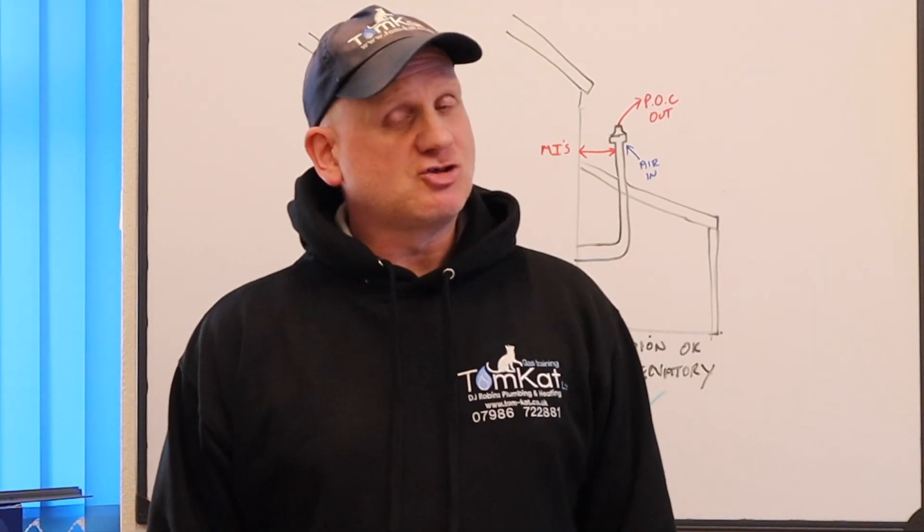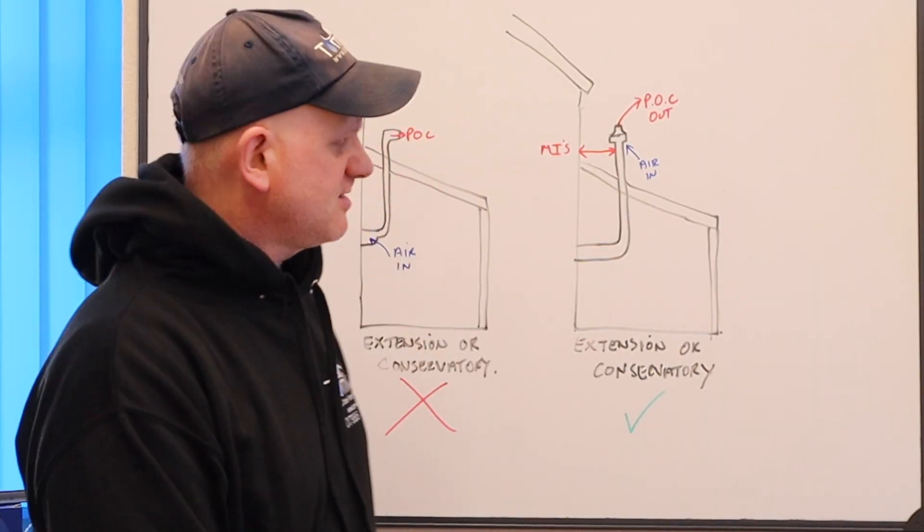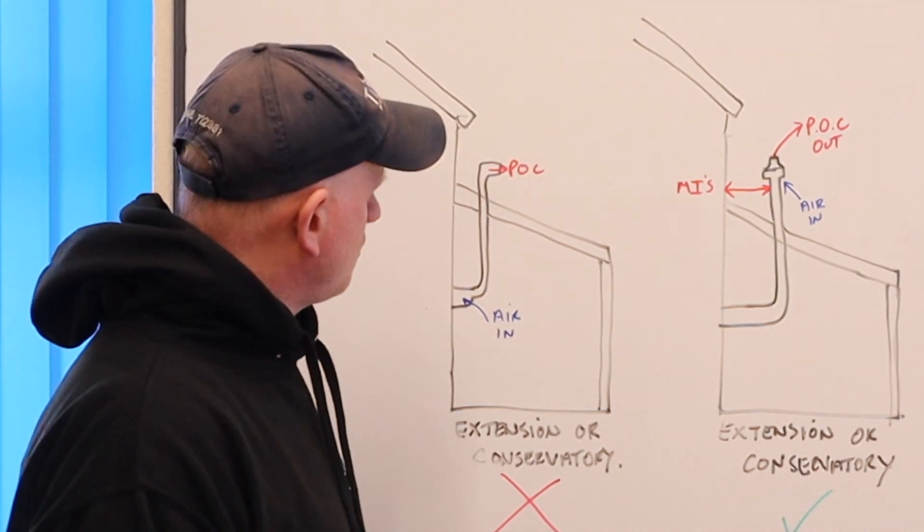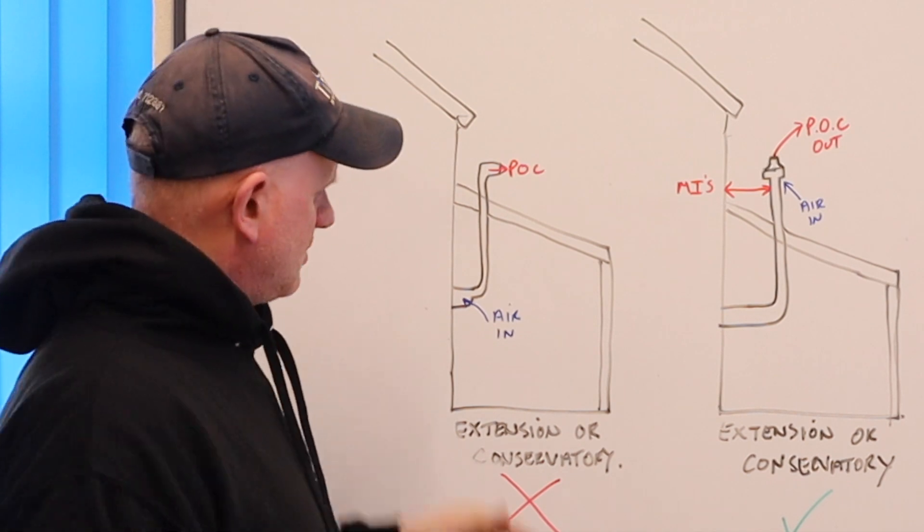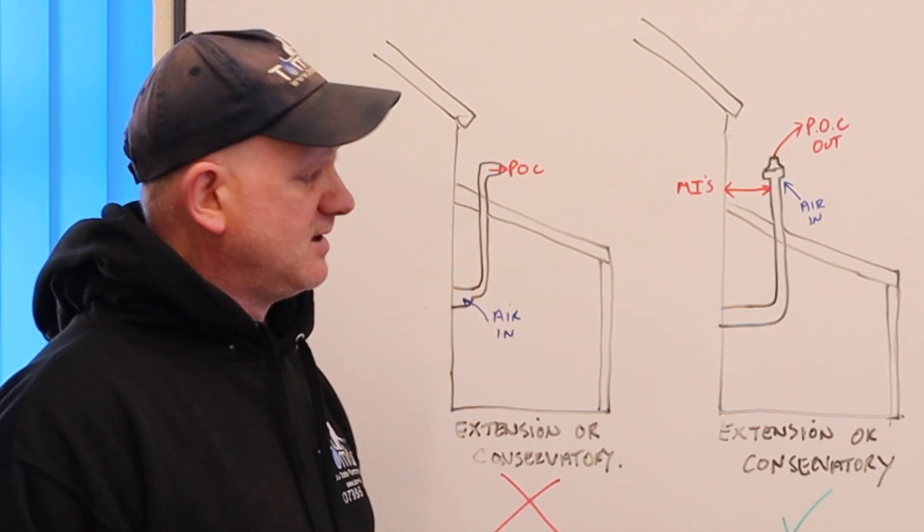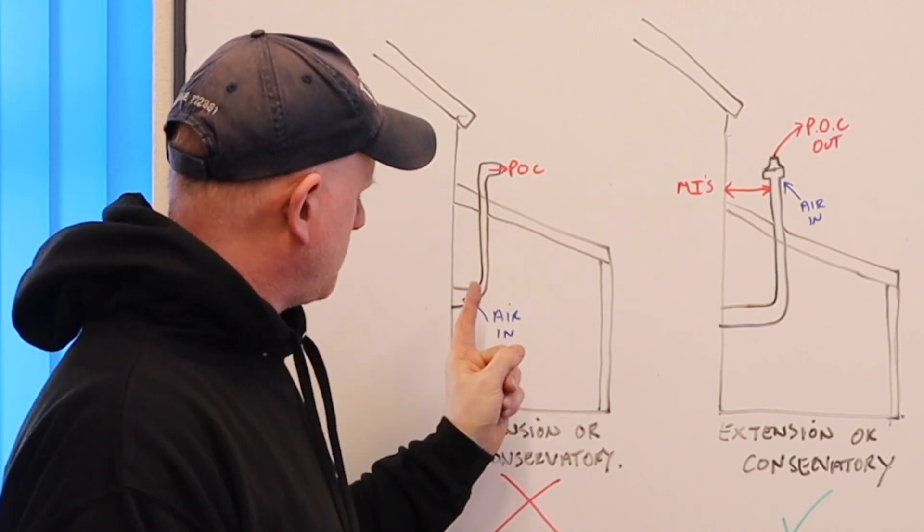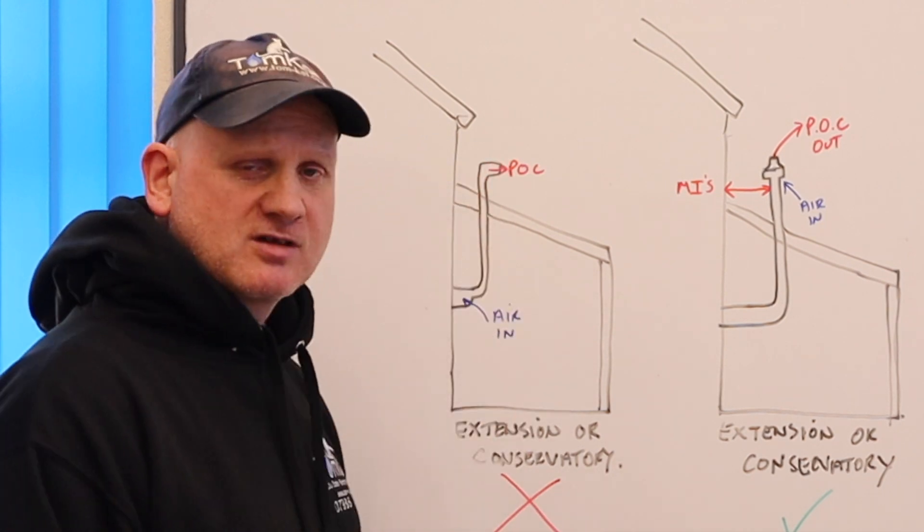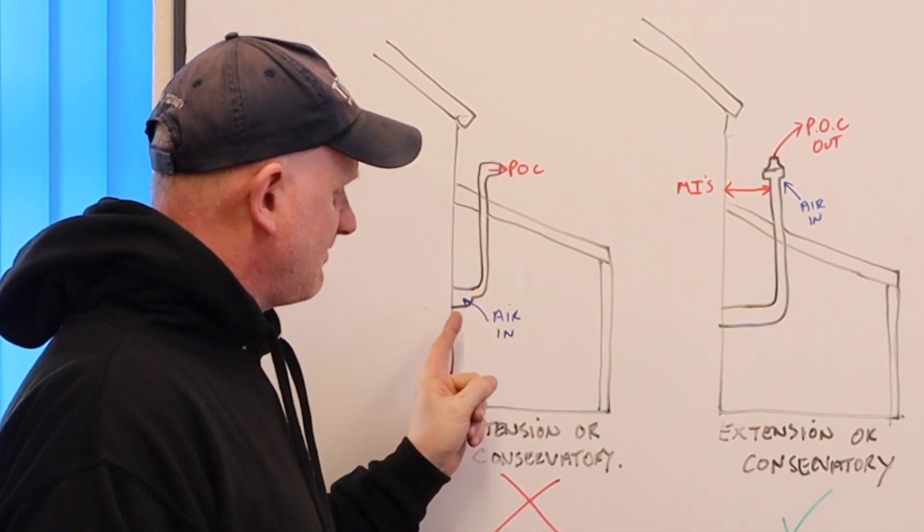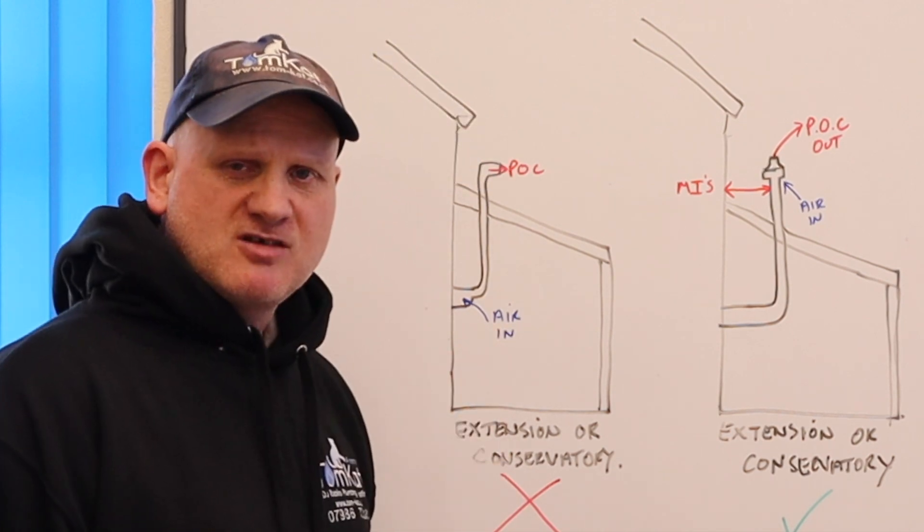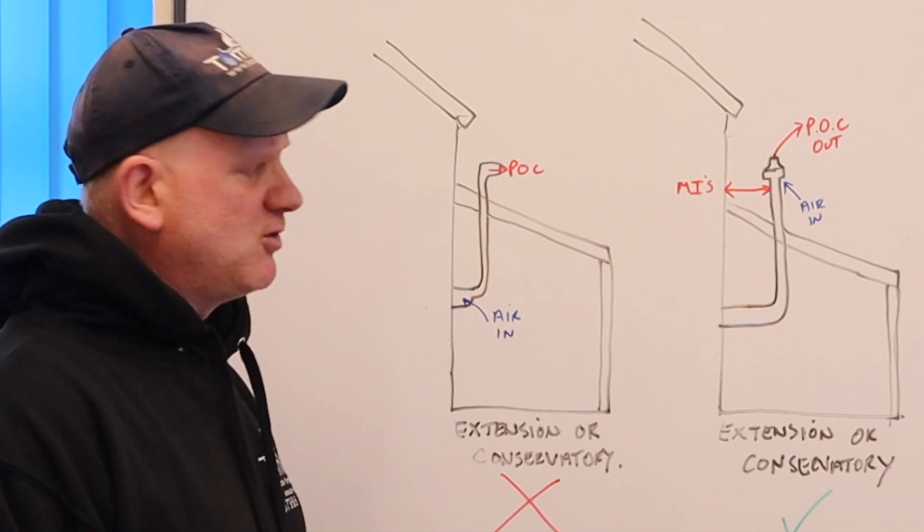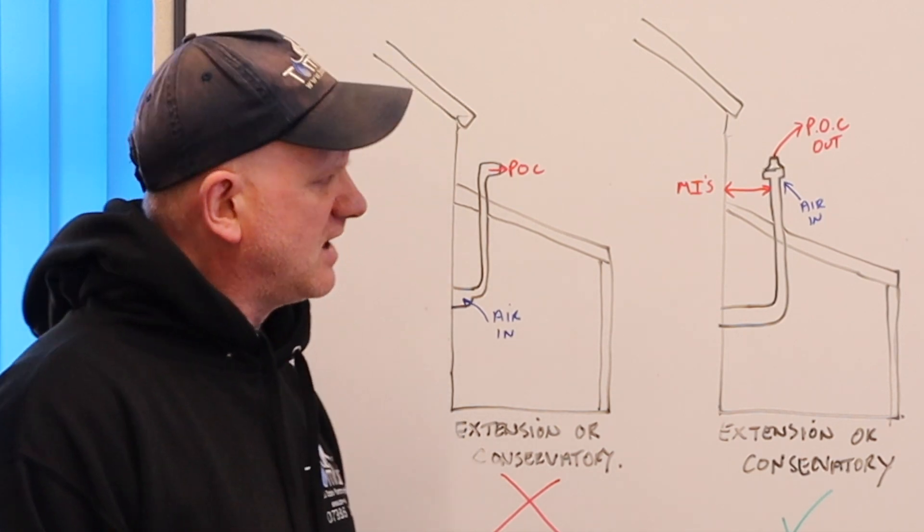Now, one of the things you can't do with a plume kit is this. So this is an extension or a conservatory and this is the old position of the flue. So the products of combustion came out here. You cannot use a plume kit to take the products of combustion out through the roof and leave the air intake coming in your kitchen extension or your conservatory. You cannot do that. And that would be deemed at risk if you did do that.